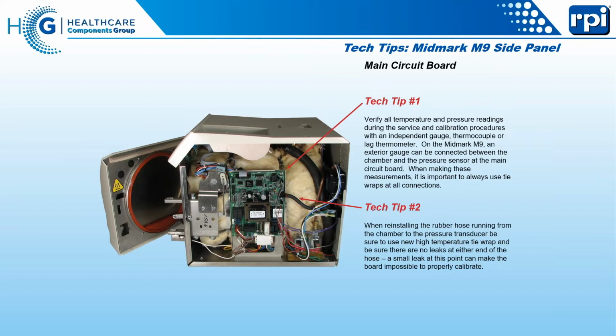But there are some things on the older machine, the -01 through 19, that you can actually do. You can calibrate that board. On both of these machines, it's possible, as we describe here, to put an external pressure gauge onto this piece of tubing, just to verify if you want that the machine is telling you the truth. But on these machines, it's not totally necessary.